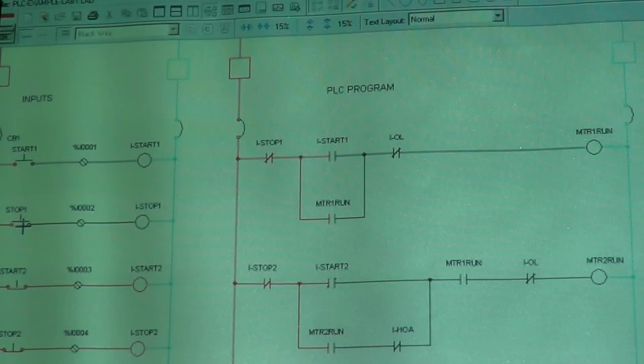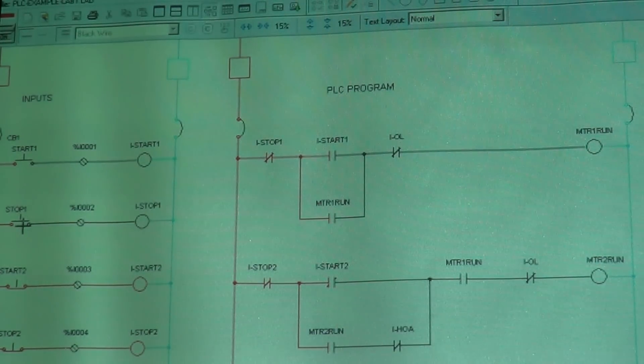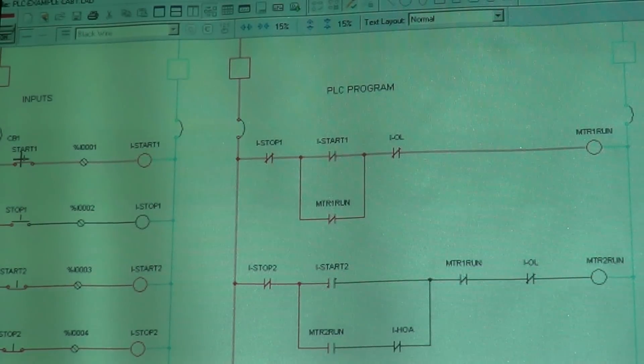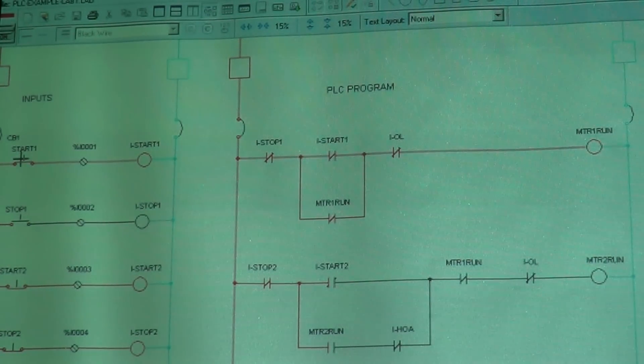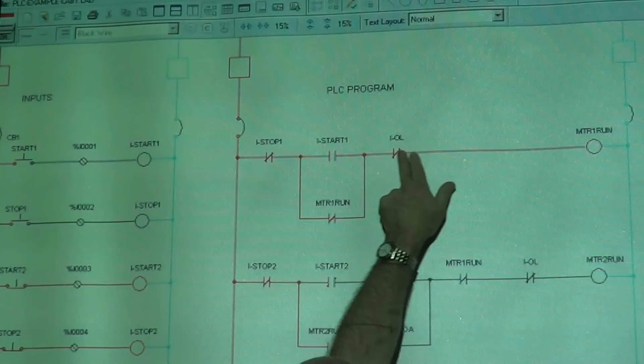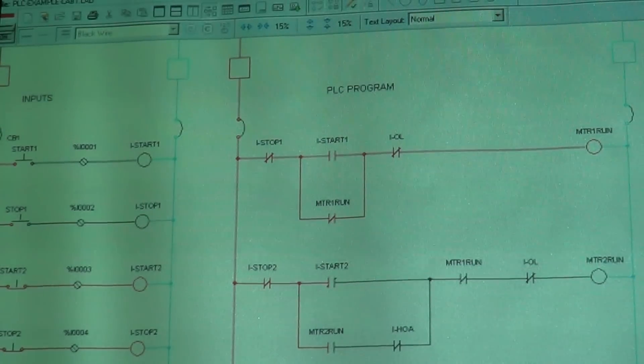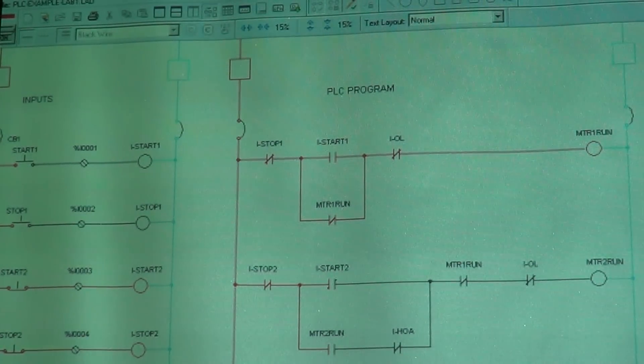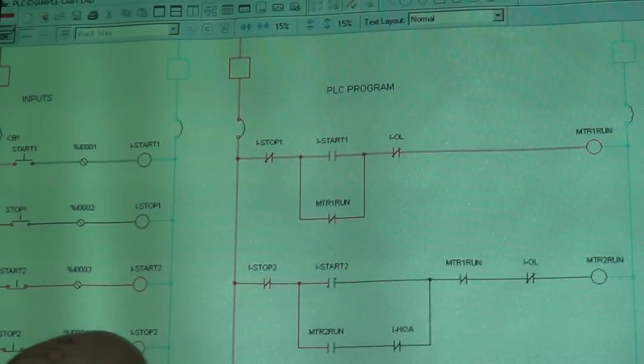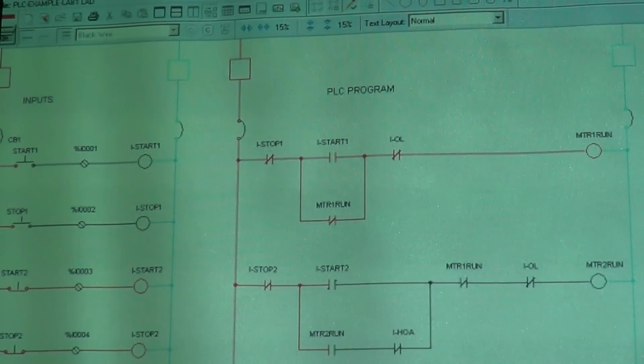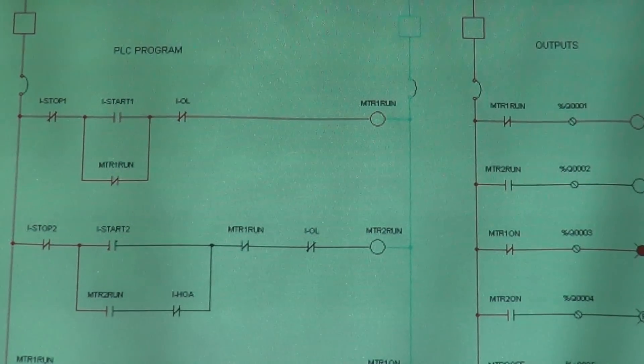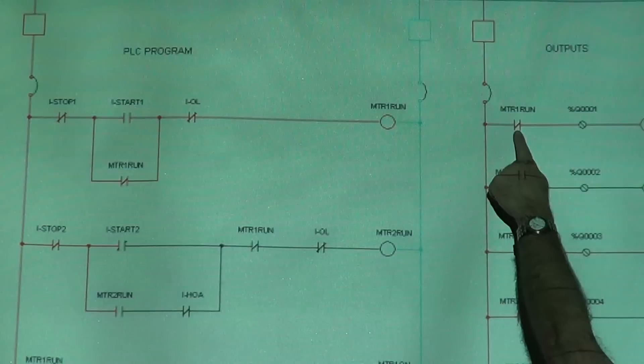You're going through a relay to control relays, so you have to keep track of what's happening. I'm going to push and hold the start button — you see the contacts on 'I Start One' are closed. Now I let go and those open. But when those were all closed, the power flow allowed me to energize that coil 'Motor One Run.' These are the holding contacts for Motor One Run. This is an internal coil Q1, connected up to Q1. You see the contacts for Motor One Run right here — the output is now energized and that output starter is on.